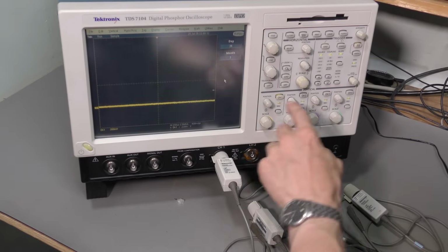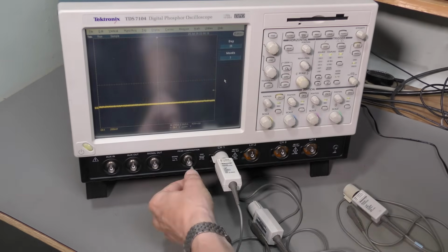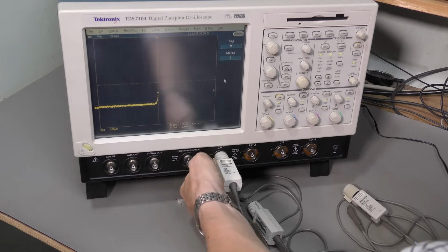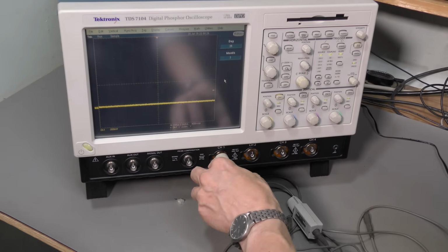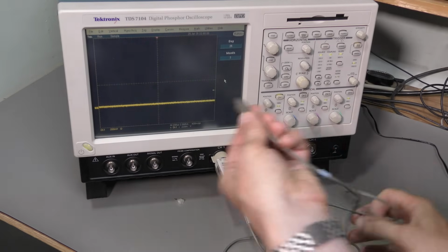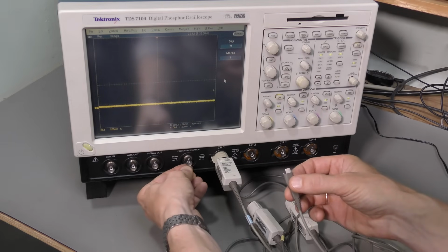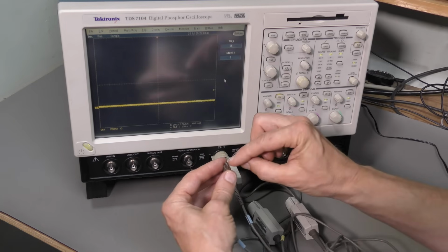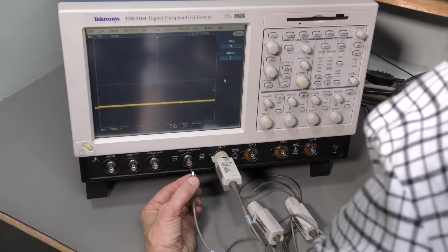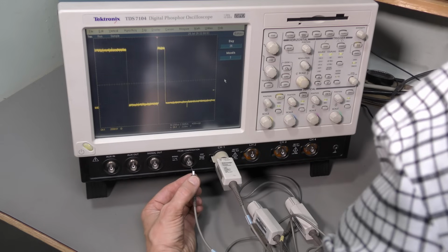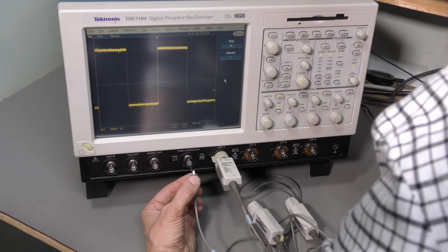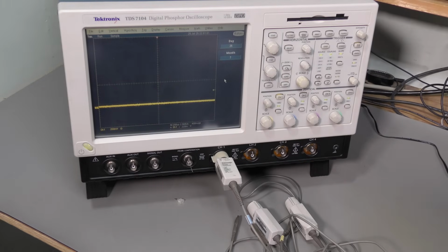Now this one, it is not recognized, there is no relay click and no 50 ohm termination, but we see the signal and the amplitude is wrong. We need to fix that. And this one is recognized. Relay clicks and 50 ohm termination is on. And now if I put this pin into the connector and very carefully touch that point on the probe tip, we can see that square wave just fine. Here it is. So let's see how we can fix them.